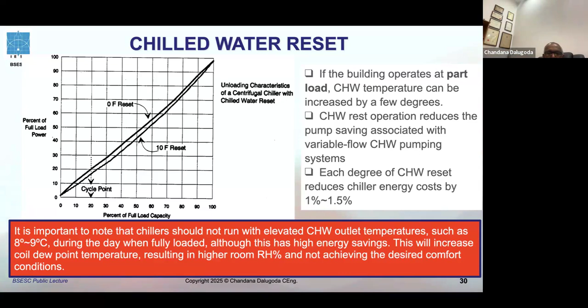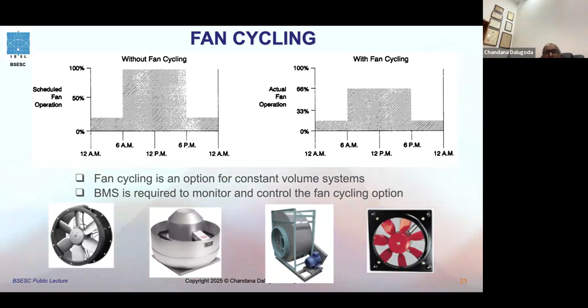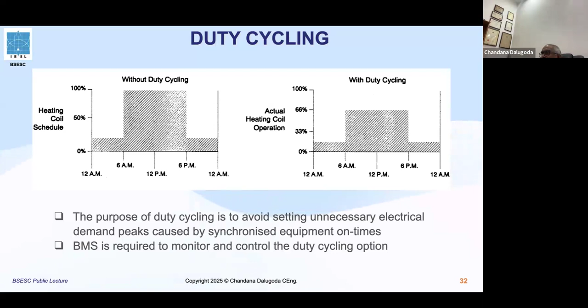Fan cycling. Fans are working constantly throughout the day, wasting energy. Sometimes you can reduce the airflow. Now VFDs are very common and very cheaply available. Why not cycle fans? Duty cycling is another energy saving strategy using BMS. This is to avoid setting unnecessary electrical demand peaks caused by synchronous equipment on times. That is called duty cycling. You stagger the startups. Optimum start-stop.